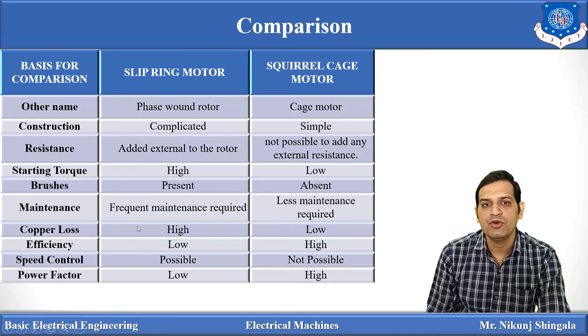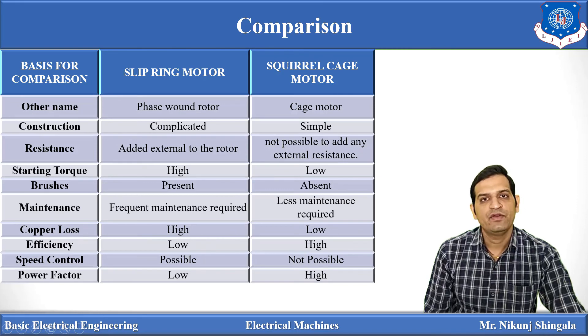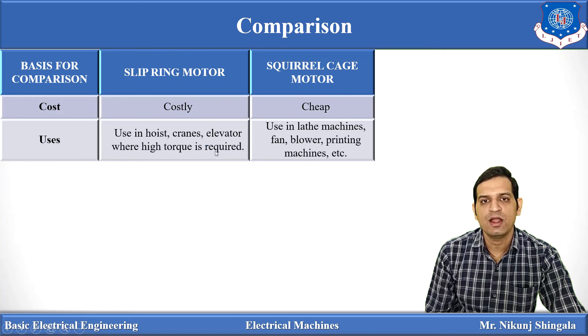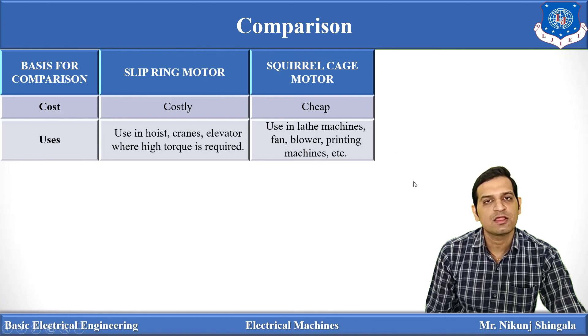Copper loss is very high in the slip ring motor and low in the squirrel cage motor. Efficiency of the slip ring motor is low, while squirrel cage motor efficiency is high. Speed control is possible in the slip ring motor by adding external resistance, but not possible in the squirrel cage motor. Power factor is low for slip ring and high for squirrel cage. Cost is high for slip ring motor due to three-phase winding, brushes, and slip rings; squirrel cage motor is less costly. Slip ring motors are used in grain elevators where high starting torque is required; squirrel cage motors are used in lathe machines, fans, and blowers where high starting torque is not required.